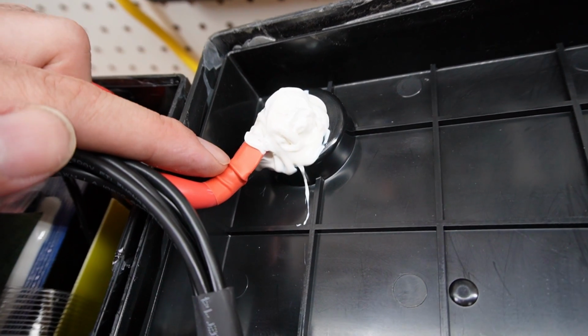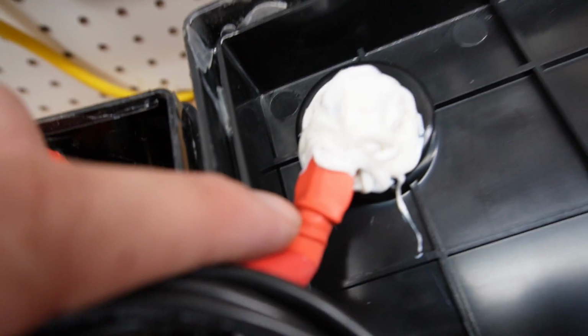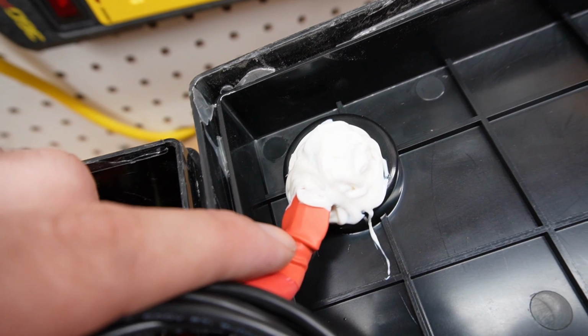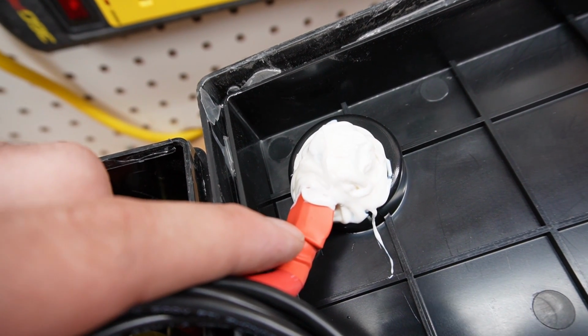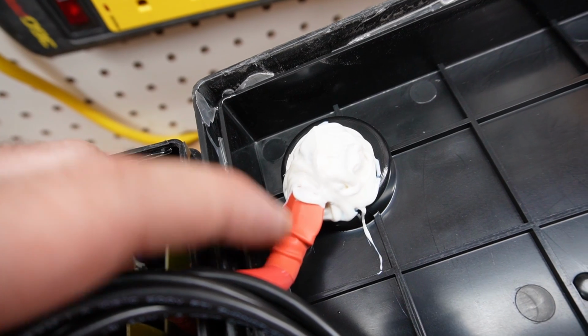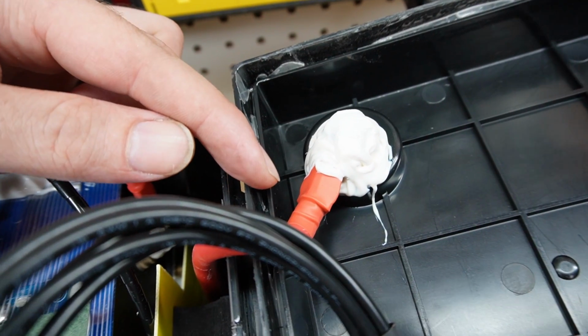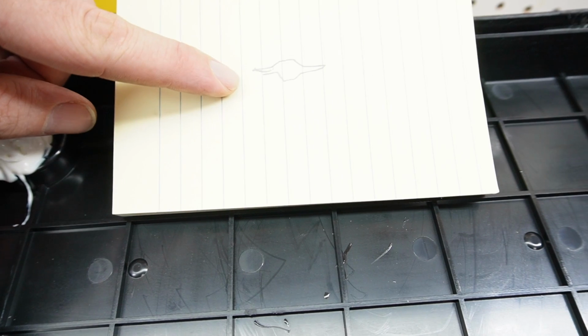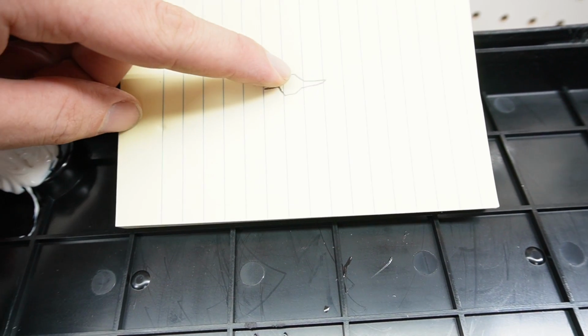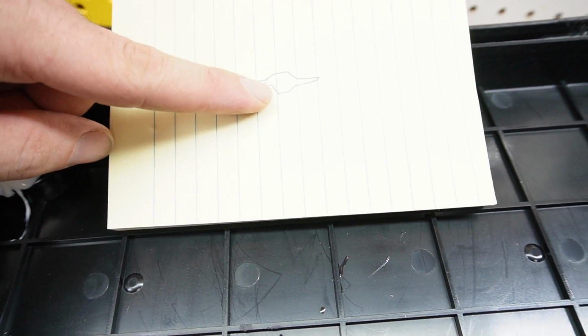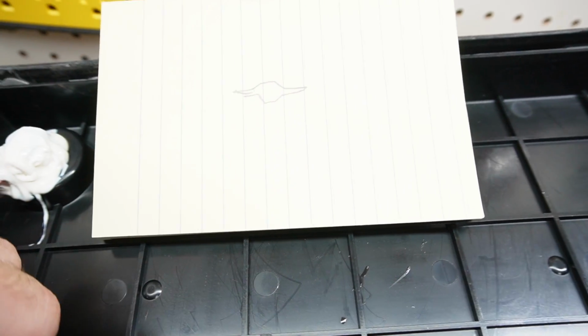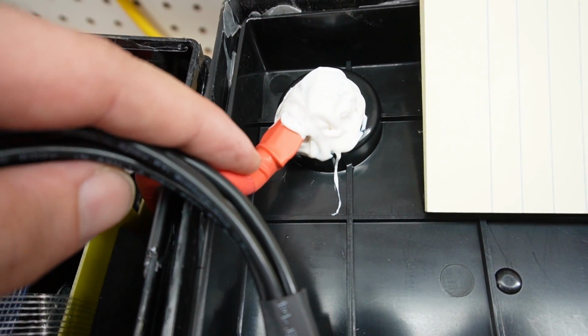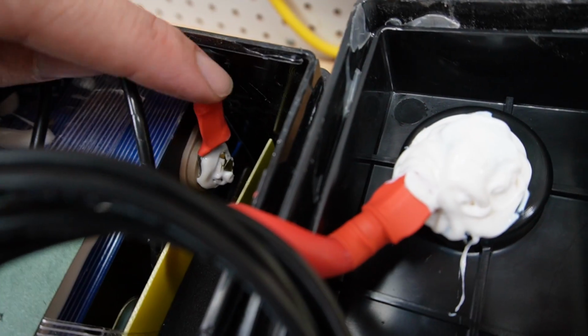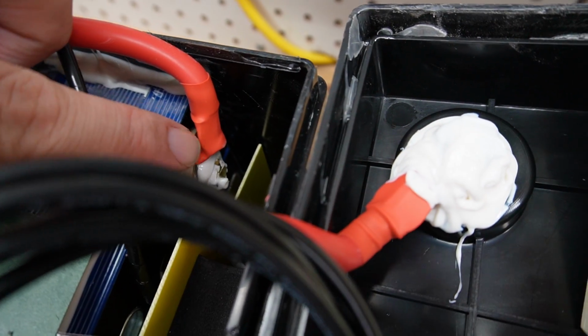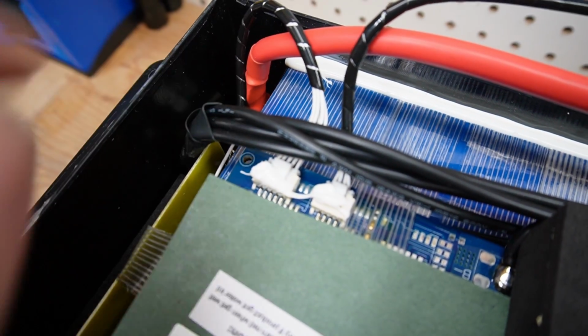Already I can tell, if you look at this crimp, I'm going to call that the butterfly effect. To me, it looks like they used a die that was too small for this gauge wire and this size of lug. The crimp came out sort of like a butterfly. Don't mind my horrible drawing, but it came out like this - you've got a space here and then a butterfly wing coming out on each side. You can see that on this crimp here, and how it's flat. Same thing on this crimp right here.